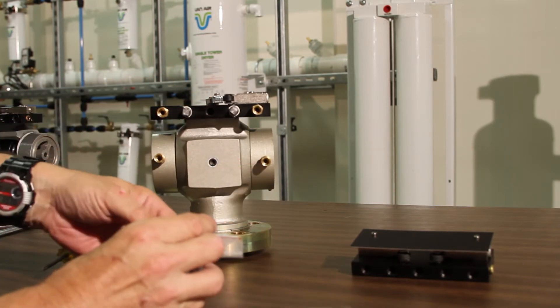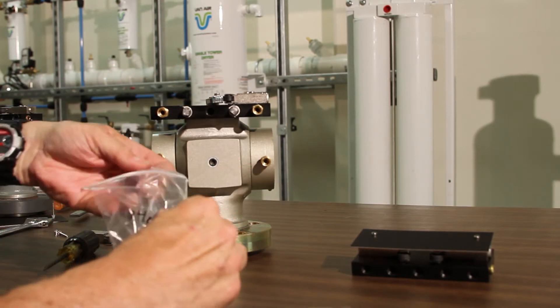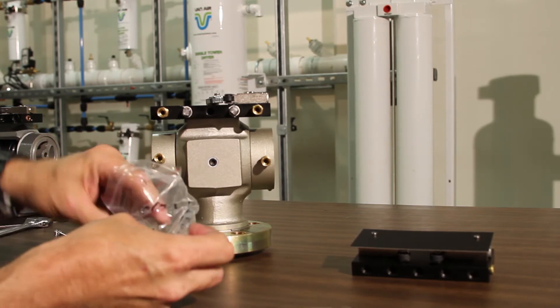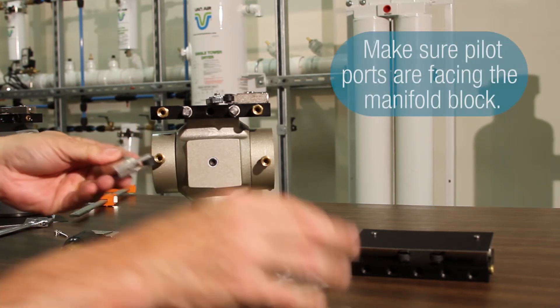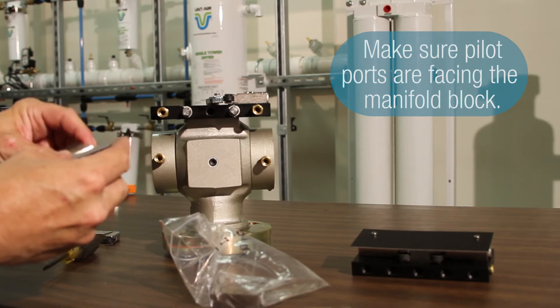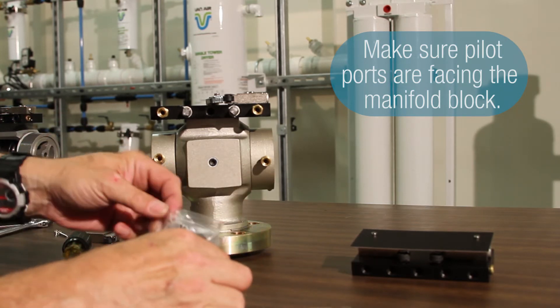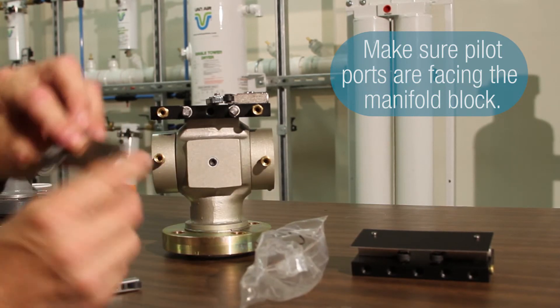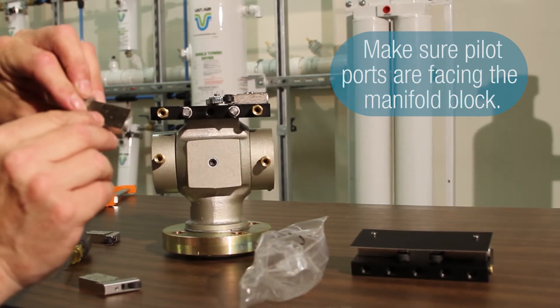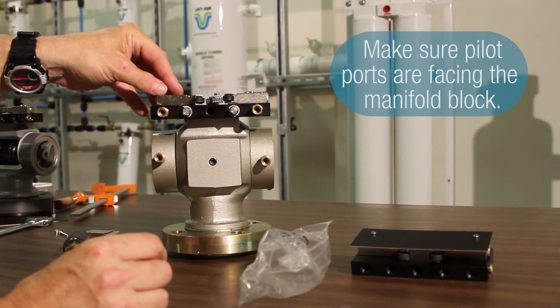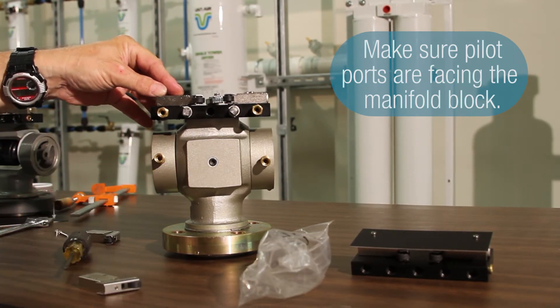So when you replace the pneumatic limit switch with a new switch, you've got to make sure that you replace it with the limit switch that seals the pilot ports for the pneumatic limit switch facing the manifold block.